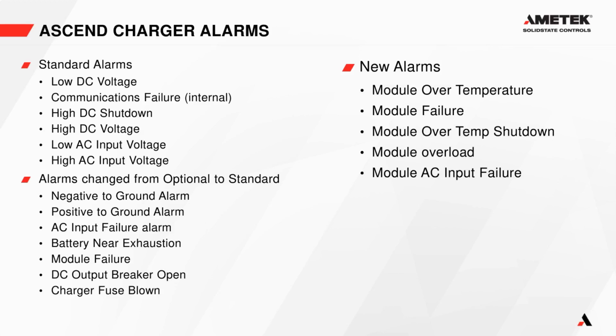So the standard alarms that are always in the Ascend charger are the low DC voltage alarm, and the communications failure alarm, which will tell you if there's a communications failure between any of the modules or the relay board that's inside the system. A high DC shutdown will shut down the charger with software if the voltage gets too high. We have a high DC voltage alarm. And then on 3-phase, we also have low AC input voltage and high AC input voltage as standard. So those are the standard alarms that were also standard on the DCR.